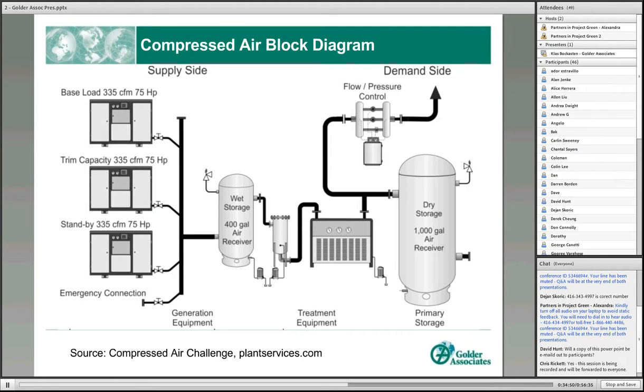What you see here is just a block diagram of a sample plant. This indicates 3 75 screw compressors. The first unit, the top one, I'll just show the indicator button here, would be the baseload machine. So say that the plant typically is consuming something like 300 plus CFM. So this would then be the baseload machine. The second one would then be the trim machine that would allow it to come on when the load in the plant would increase. And the third one, in a good installation, would be a standby compressor, simply available in case of breakdown or some extreme condition in the facility.